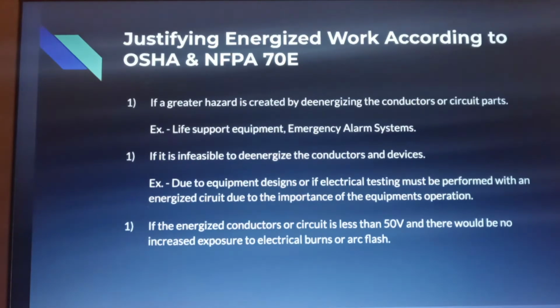So, justifying energized work according to OSHA and the NFPA 70E. There's really only three points to justify working on something hot. And that is if there's a greater risk created by de-energizing the conductors or circuit parts, like a life support system or emergency alarm system, or lighting from an exit, stuff like that. It's more important to have it on than it would be to have it off.